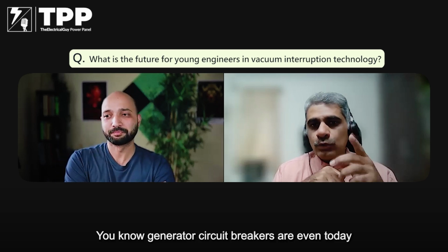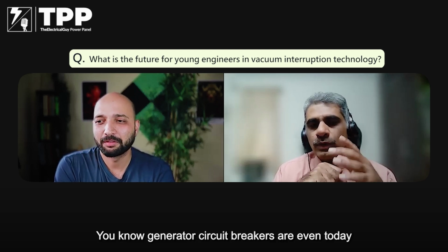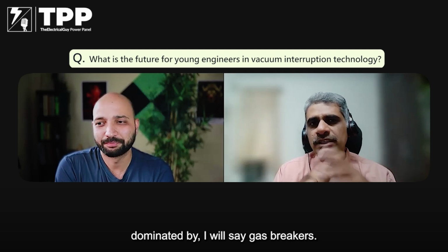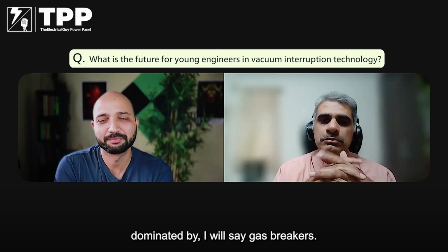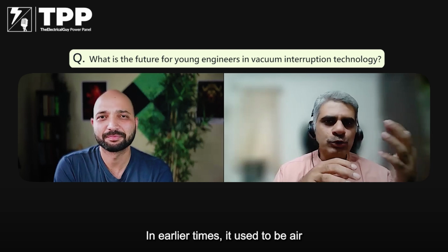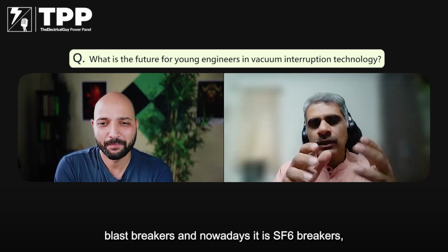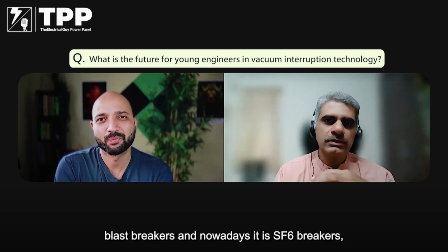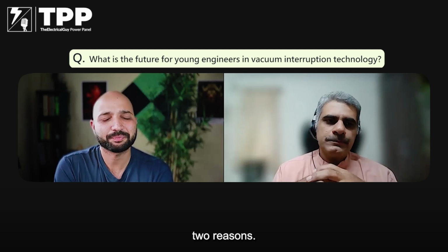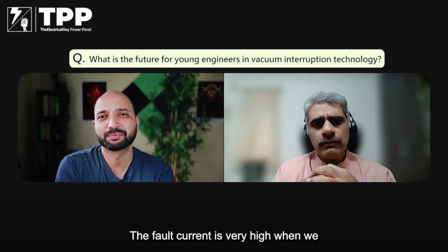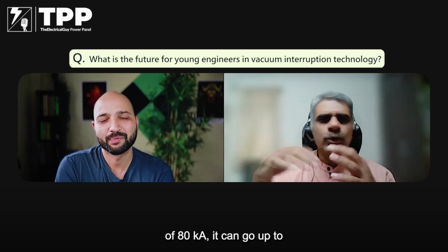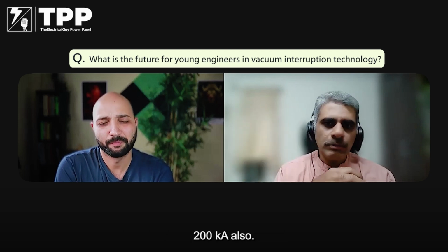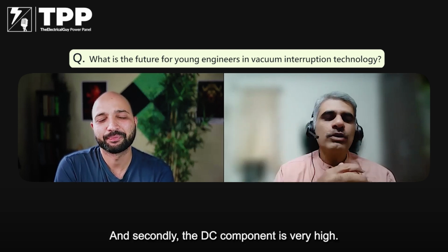Generator circuit breakers are even today dominated by, I will say, gas breakers. In earlier times, it used to be air blast breakers, and nowadays it is SF6 breakers. Two reasons. The fault current is very high. When we talk about generator breakers, it's upward of 80 kiloampere. It can go up to 200 kiloampere also. And secondly, the DC component is very high.